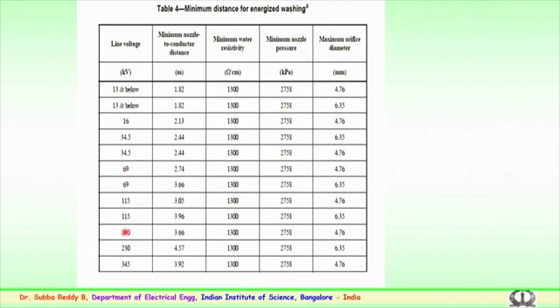Similarly, for 66 kV, 230 kV and above 400 kV, 800 kV, the values could be slightly different, and the distances could also change. So, these are the minimum distances for energized washing, because proper precaution has to be taken as it is live line washing. So, suitable care has to be employed. These have to be strictly followed: the conductivity, the minimum pressure, and all this are given in the standards.